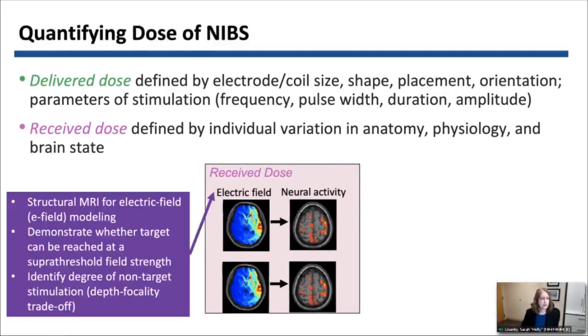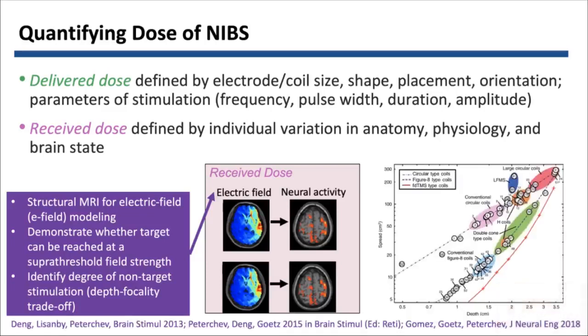We have tools that allow us to quantify, for example, the electric field using structural MRI to model and simulate the electric field. There are also new approaches to image the electric field by imaging the magnetic field generated by the electric field generated in the brain. This can be very useful in demonstrating whether a target can be reached and identifying the degree of non-target stimulation. There's a fundamental depth-focality trade-off — here you're seeing different TMS coils modeled with depth on the x-axis and degree of spread on the y-axis.